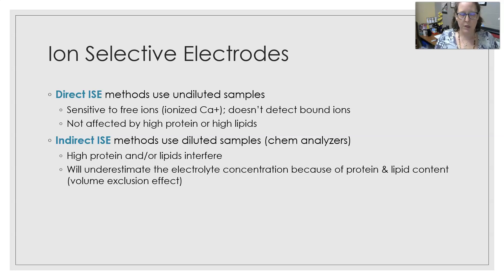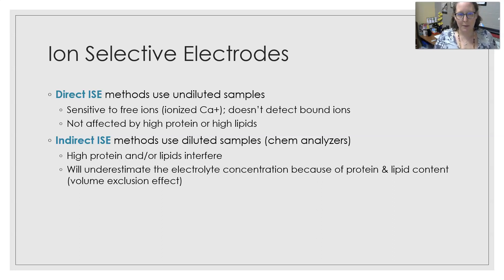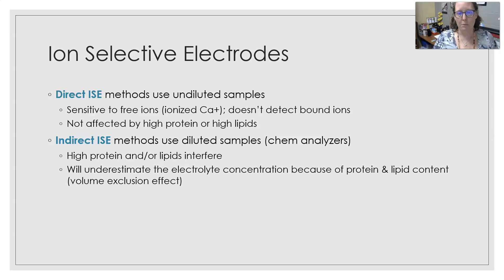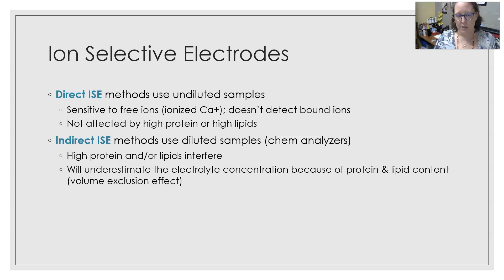Direct ISE methods are very sensitive to free ions but do not detect bound ions. The advantage is that they are not affected by high protein or high lipid content. This method is often used to measure ionized calcium. The indirect ion selective electrode methods use diluted samples and are used in most large chemistry analyzers. However, high protein content and lipemia can interfere with readings and tend to underestimate electrolyte concentration — this is called the volume exclusion effect.